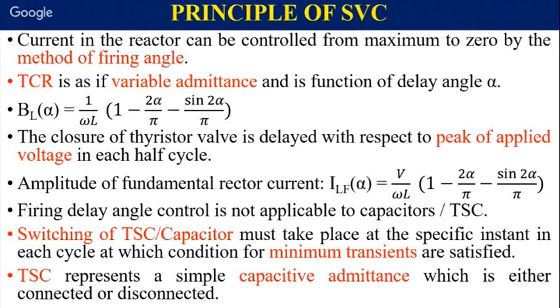So the susceptance of a reactor, or inductive reactance: since it is connected in parallel, it is susceptance. It is a function of the delay angle alpha, which is given by 1 upon omega L, times (1 minus 2 alpha by pi minus sine 2 alpha by pi). Since closure of the thyristor valve is delayed with respect to the peak of the applied voltage, because it is an inductor, its characteristic is that current lags voltage by 90 degrees.